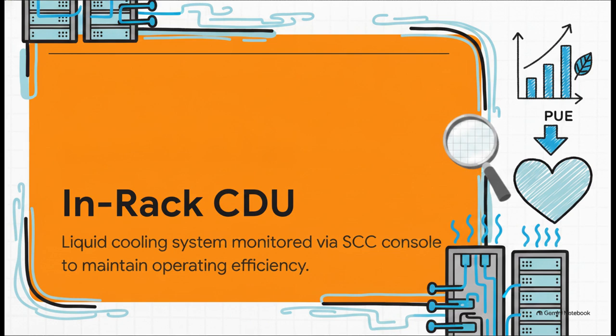The core piece of hardware doing the heavy lifting here is the in-rack CDU, or coolant distribution unit. Think of this as the beating heart of your liquid cooling setup. By keeping a close eye on these units through the SuperCloud Composer console, administrators can maintain peak operating efficiency in their high-power racks.